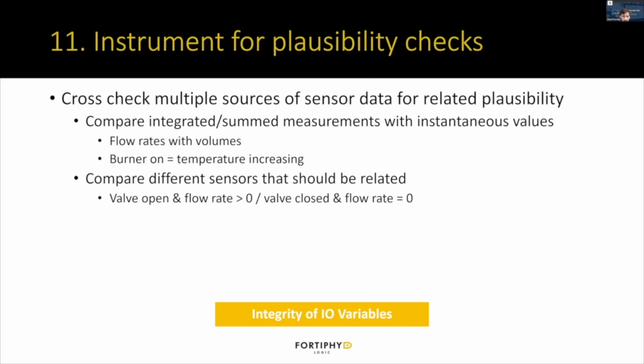Another approach is, for example, if the burner is on, the temperature should be increasing. Just having a check in there: do things seem to be behaving like they should? If the burner's on, the temperature should be increasing. If it's not increasing, then maybe the burner is not actually heating things up, maybe you have some other problems, maybe an attacker is injecting false data into the control system. Other approaches are just comparing different sensors that should be related. If the valve is open, then the flow rate should be greater than 0. It could be a simple check. Or if the valve's closed, the flow rate going through that valve should be 0.